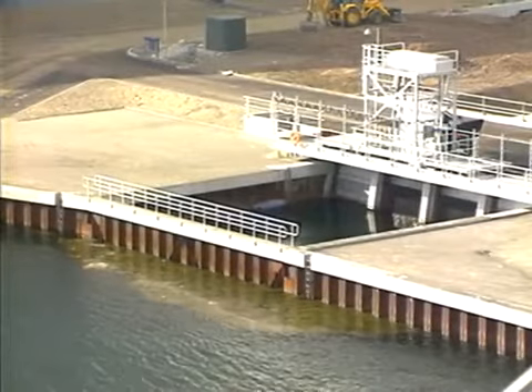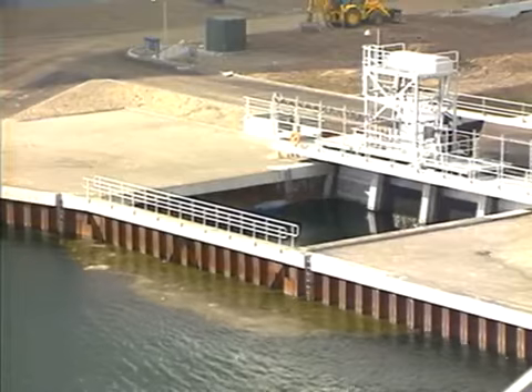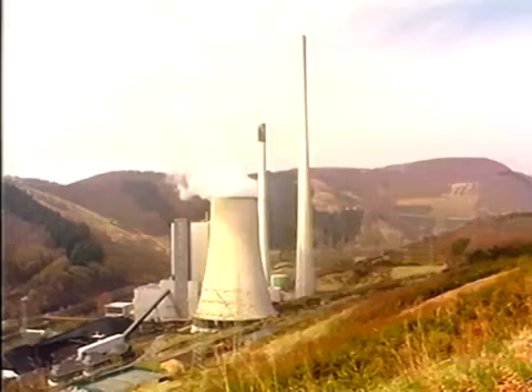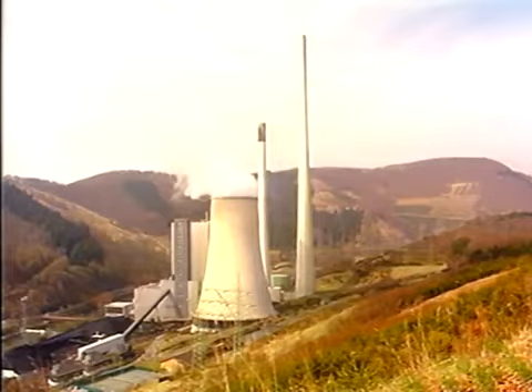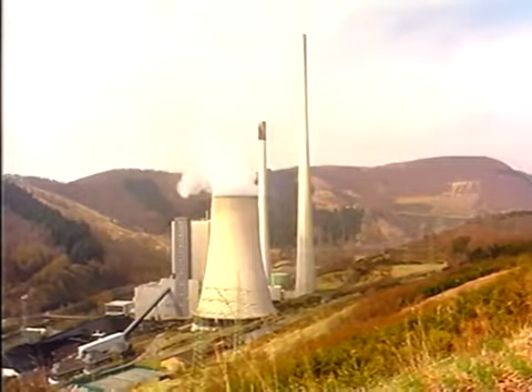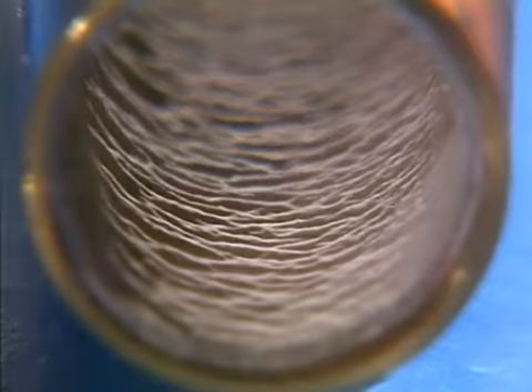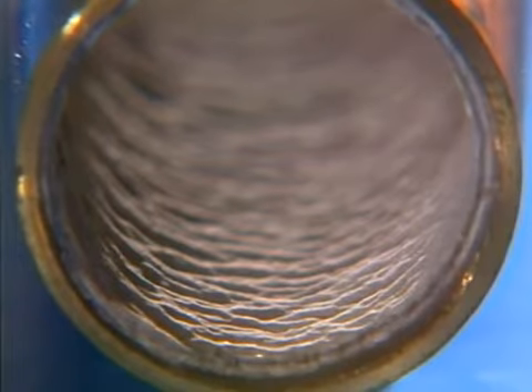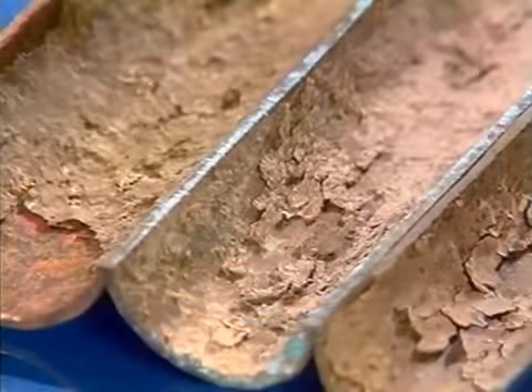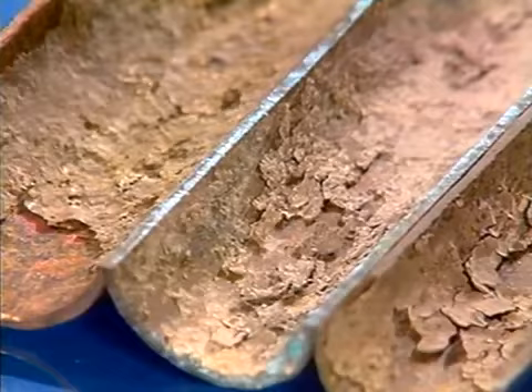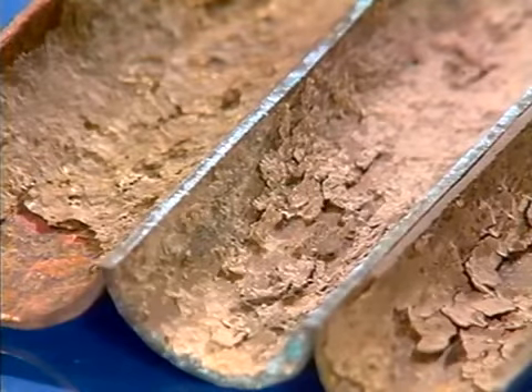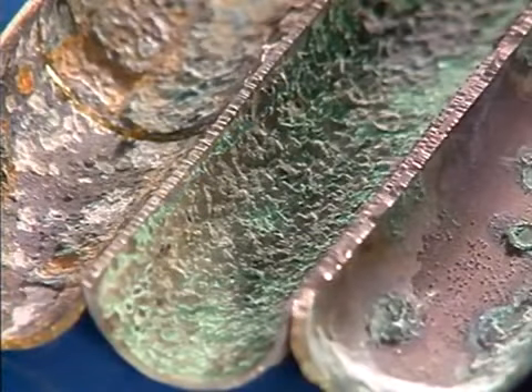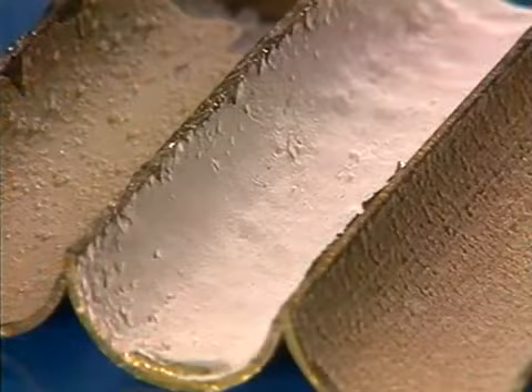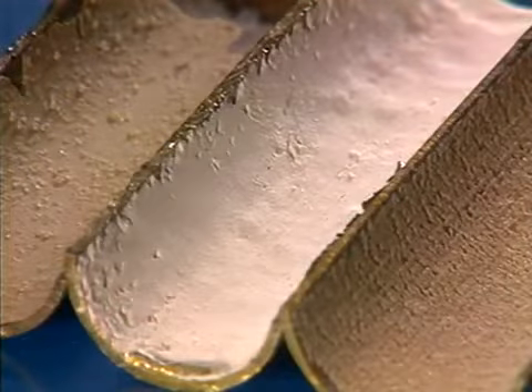This cooling water is taken either from a river or from the sea in an open cycle, or it circulates in closed cycle with cooling tower operation. In the process, particles in the water contaminate the inner surface of the tubes. River water, for example, typically fouls the tubes with layers of mud. Seawater causes bioslime and sediment, while cooling tower systems attract deposits of calcium carbonate.